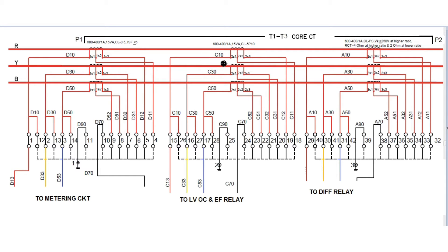The specification for the protection overcurrent core: CT ratio is the same, rated burden is 15VA, and class is 5P10. What does 5P10 mean? If 10 times the rated current flows on the HV side under rated burden condition — that is, the secondary rated burden is 15VA — then the maximum error will be 5%.